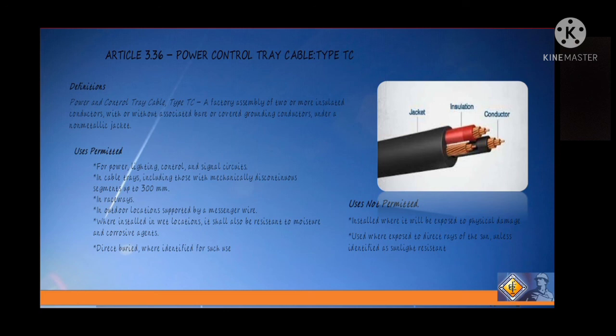In terms of uses permitted, it is used for power, lighting, control, and signal circuits in cable trays, including those with mechanically discontinuous segments up to 300 mm. It is also used in a raceway, and in outdoor locations supported by a messenger wire. Where installed in a wet location, it shall also be resistant to moisture and corrosive agents, and direct buried if identified for such use. In terms of uses not permitted, it is not used where exposed to physical damage, and where exposed to direct rays of the sun unless identified as sunlight resistant.